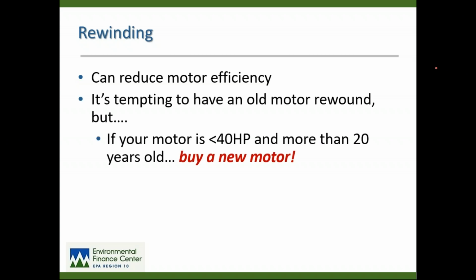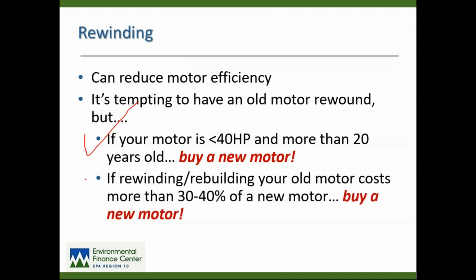Rewinding is very tempting, to go and have your motors rewound because it's less expensive than buying a new motor, and you are basically getting almost a new motor. But these are my rules of thumb. If your old motor is more than 20 years old and less than 40 horsepower, just go buy a new motor. I can almost guarantee you that energy savings will pay back the cost of that motor well within its lifespan. If rebuilding your old motor costs more than 30 to 40% of a new motor, just go buy a new motor. Again, make sure the nameplate says NEMA Premium Efficiency. NEMA is National Electrical Manufacturers Association. I guarantee you, you will save money.